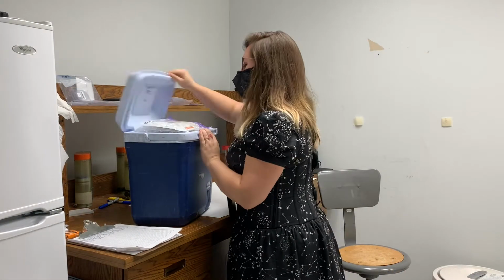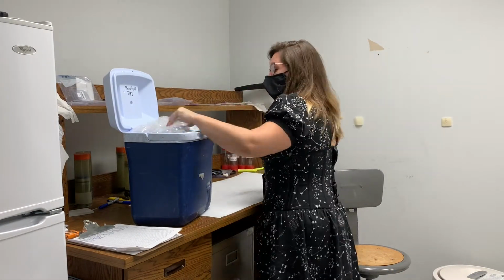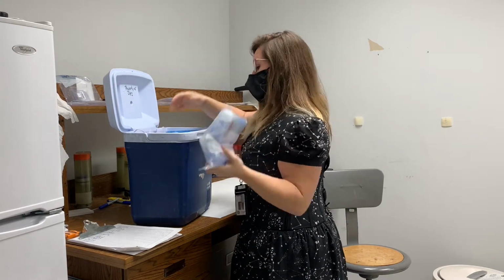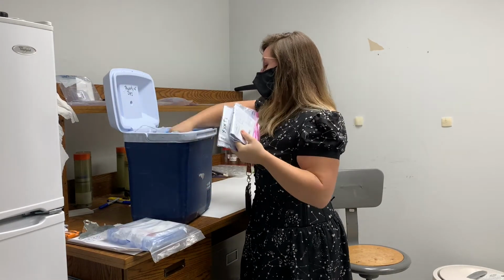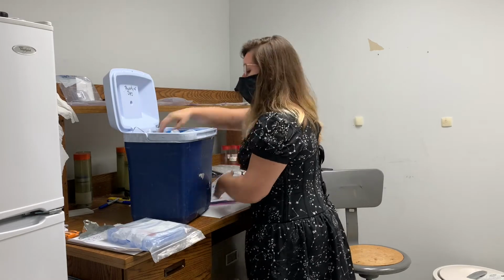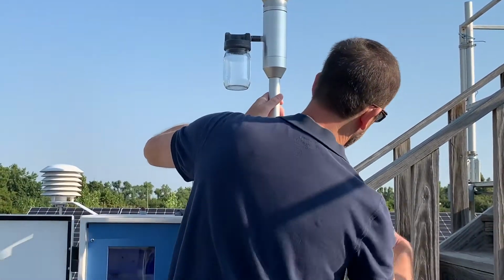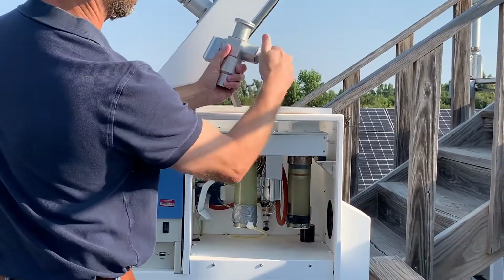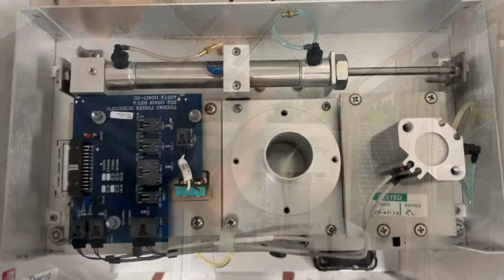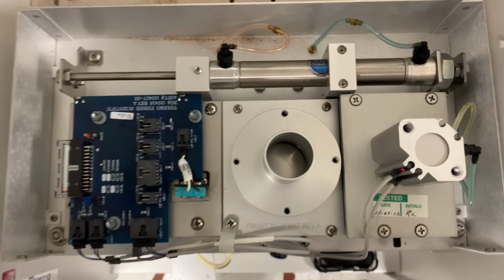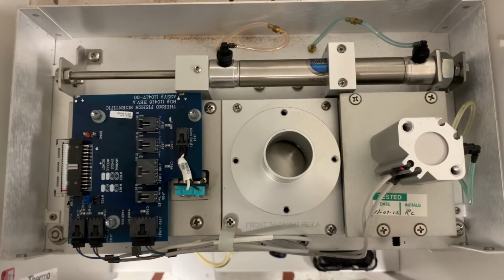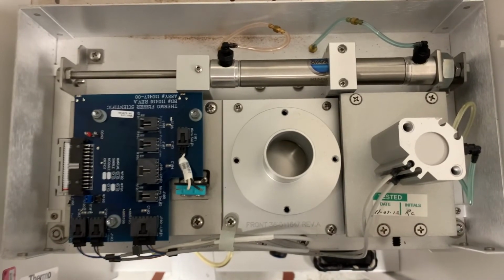For a filter-based instrument, the operator receives pre-weighed filters from a lab. They are then placed in a clean room where they are loaded into a sealed magazine and taken to the site. The filters are placed in the instrument, and the instrument is programmed to turn on for 24 hours for each filter. After the filters have collected their samples, the operator is required to retrieve the filters within a few days to prevent mass loss due to heat.